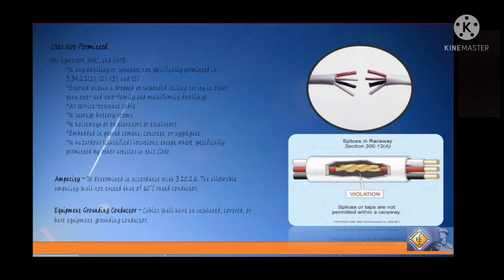So for the ampacity, the ampacity shall be determined in accordance with Section 3.10.2.6, and the allowable ampacity shall not exceed that of a 60 degrees Celsius rated conductor. In terms of the equipment grounding conductor, the cable shall have an insulated, covered, or bare equipment grounding conductor. So we can see the violation in type NM, NMC, or NMS. We can see the picture on the right side of our slide.